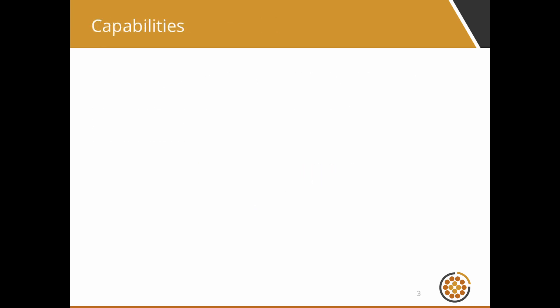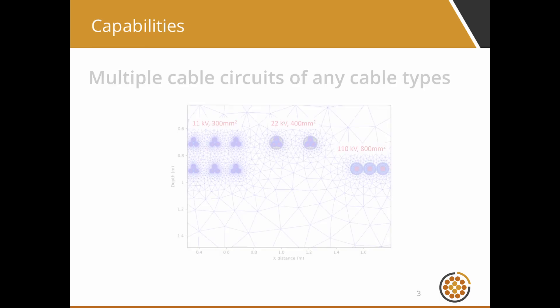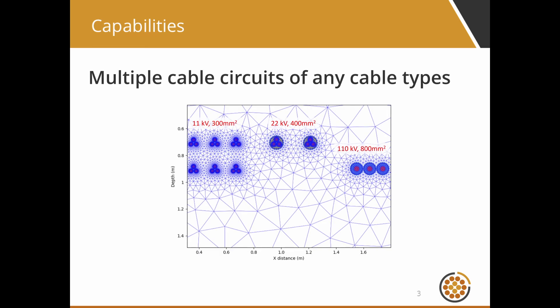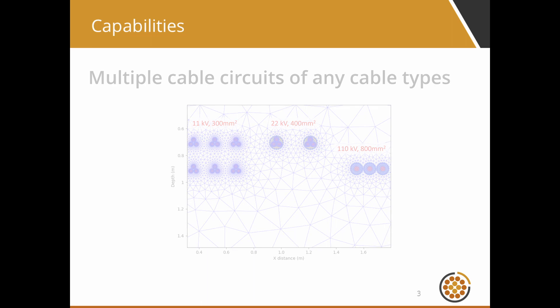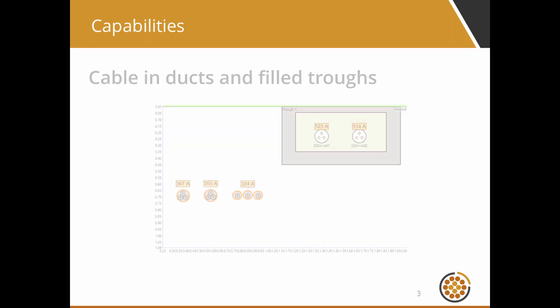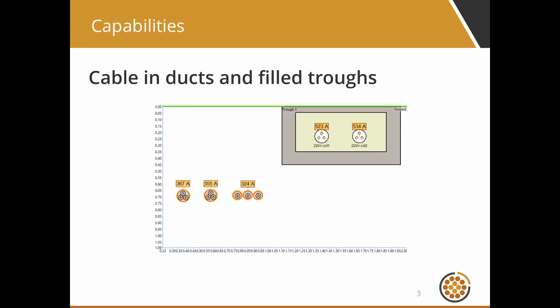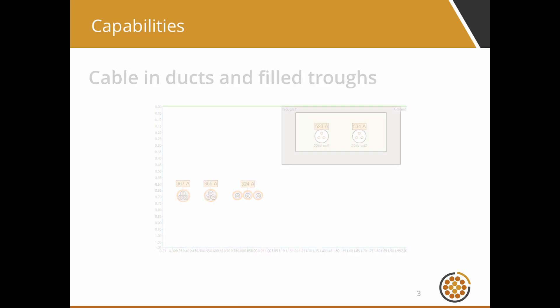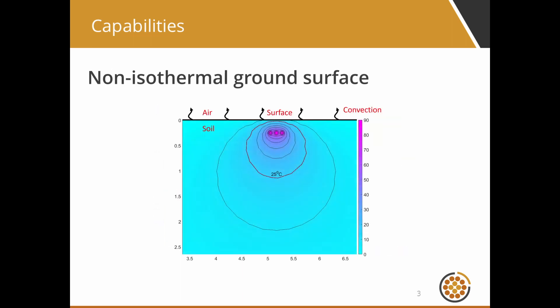The FEM module is capable of modelling the following: multiple cable circuits of any cable types, multiple backfills or zones of different thermal resistivity, cables in ducts and filled troughs, and non-isothermal ground surface with custom air velocity.